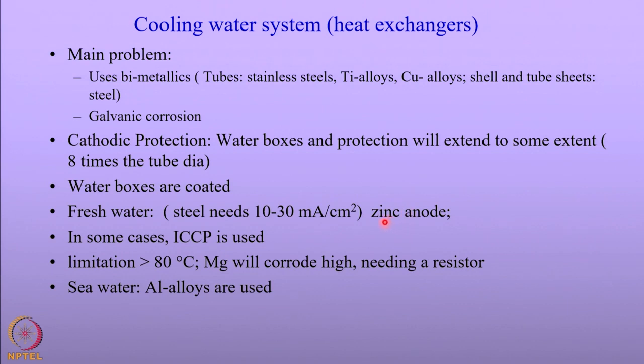However, if the temperature goes beyond 80 degrees Celsius, zinc anodes cannot be used and magnesium anodes are needed. But if magnesium is used, it corrodes very rapidly and offers over-protection, requiring a resistor to control the current delivered for protection of the structures.